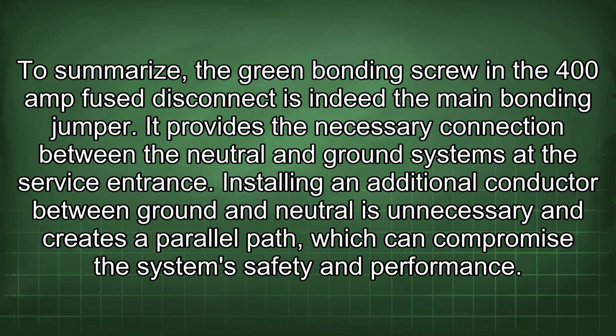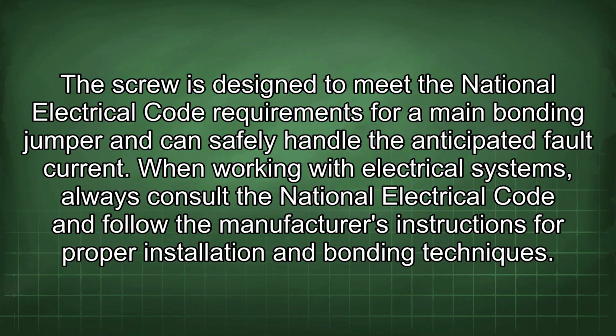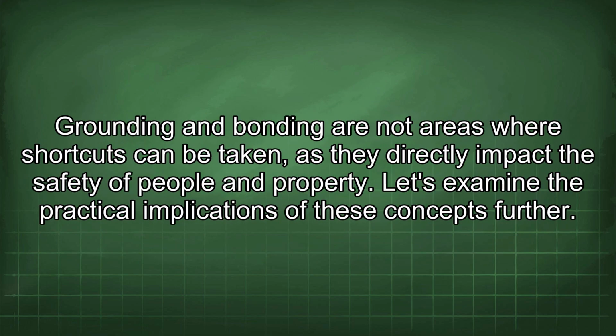Installing an additional conductor between ground and neutral is unnecessary and creates a parallel path which can compromise the system's safety and performance. The screw is designed to meet the National Electrical Code requirements for a main bonding jumper and can safely handle the anticipated fault current. When working with electrical systems, always consult the National Electrical Code and follow the manufacturer's instructions for proper installation and bonding techniques. Grounding and bonding are not areas where shortcuts can be taken, as they directly impact the safety of people and property. Let's examine the practical implications of these concepts further.